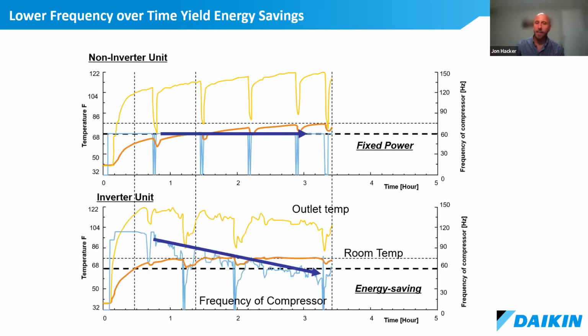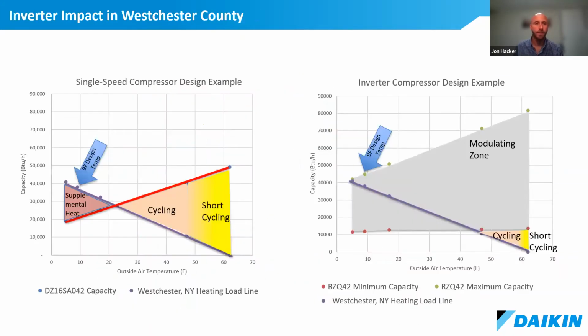And basically, we get savings from reducing the speed of the compressor. So over time, as that system learns how to precisely match the set point, it can operate more efficiently, and we get energy savings. So, we're kind of layering topics now. I've shown how we move from a cycling line to a modulating zone. And now I want to show what this really means for an application.